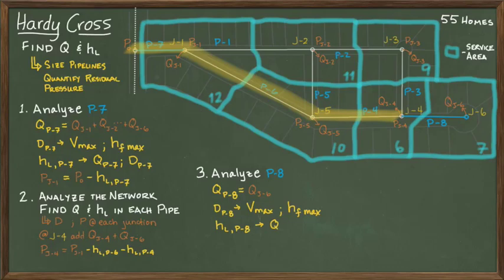And just as before, the head loss is found using the actual pipeline diameter. The final step is to compute the residual pressure at junction six by subtracting the head loss from pipe eight and the residual pressure found at junction four.